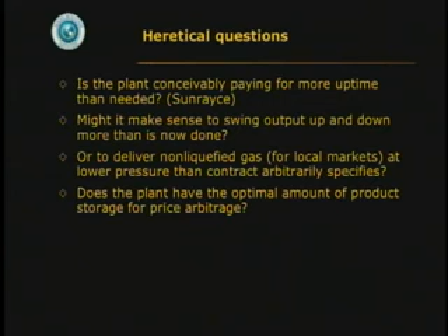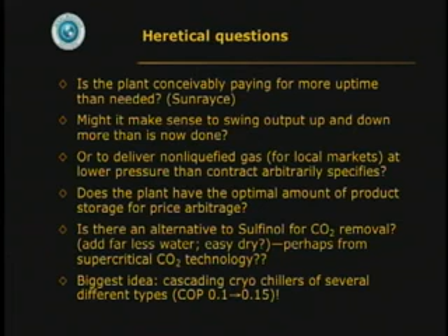And then the heretical questions to ask: Is the plant more reliable than needed? Should we swing output up and down more seasonally than is done? Deliver non-liquefied gas locally at a lower pressure than the contract says, because they just let it down again - they don't need the pressure. Do we have the right amount of storage? Are there better process improvements? There are ways to cascade the cryo chillers, the really big load, several different types, to make it about half again as efficient.